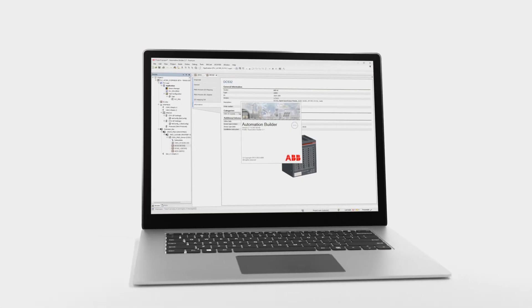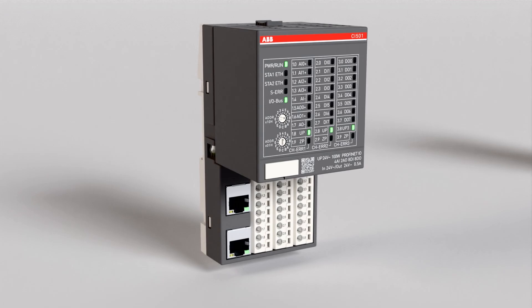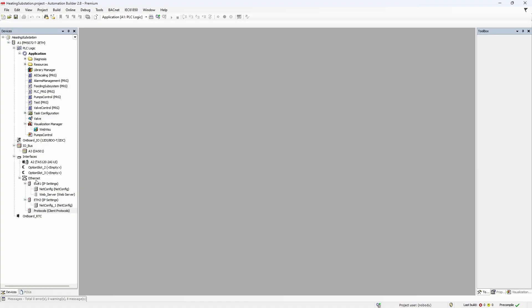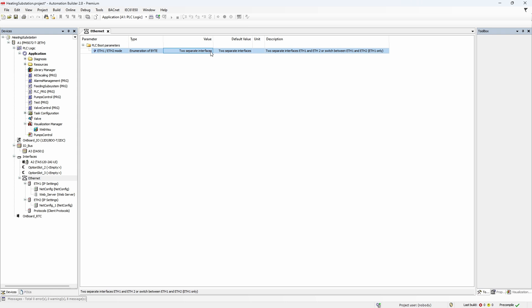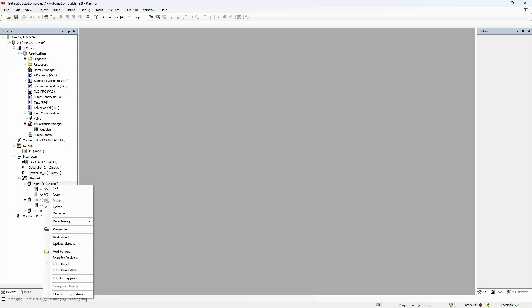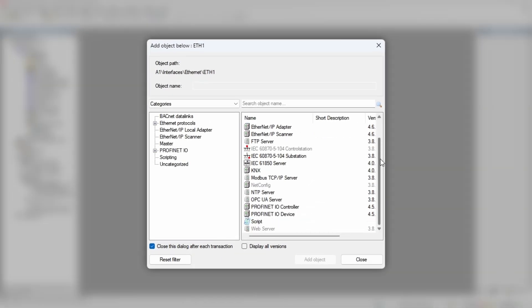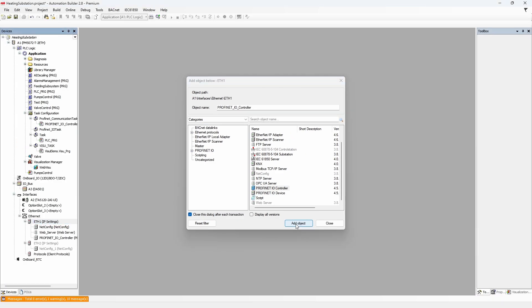First, since we are going to connect Automation Builder and CI501 remote I.O. station to the PLC at the same time, it is convenient to change embedded Ethernet ports to a switch mode rather than two separate ports. Next, right-click on the Ethernet port and add new object. You're looking for the PROFINET I.O. controller. Add object and close the window.